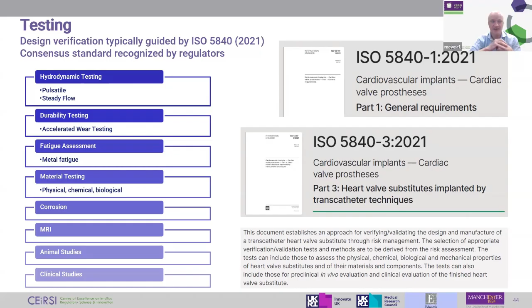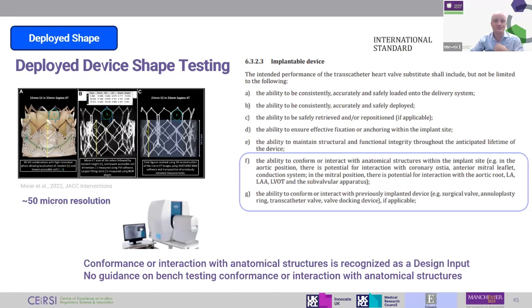Top left, I've just highlighted the context of use that the slide is relevant to. First up is the deployed shape. I'll read some text on the right-hand side: the intended performance shall include an ability to conform or interact with anatomical structures. Of course, that needs an understanding of the deployed shape. There's no detailed or prescribed testing in the standard for deployed shape. It doesn't tell you how to test the deployed shape of the device. But we do know that there are good, well-accepted testing approaches out there for characterizing the deployed shape of the device. I've given the example here of micro CT, which is pretty accurate these days and can be used for that. Next slide, please.